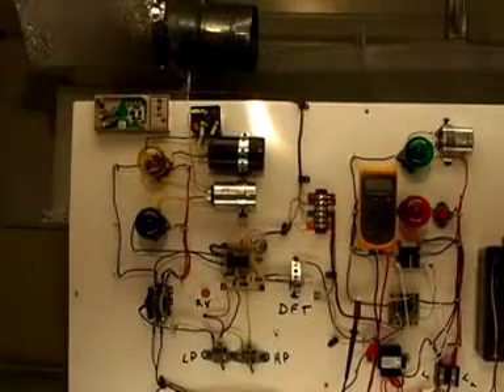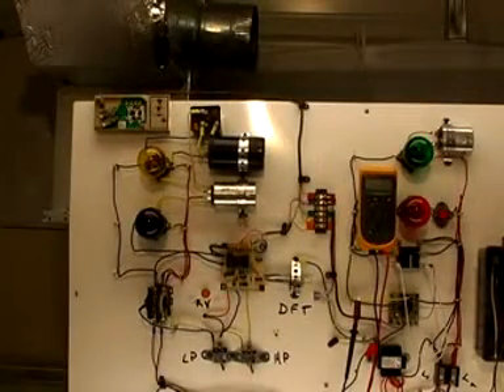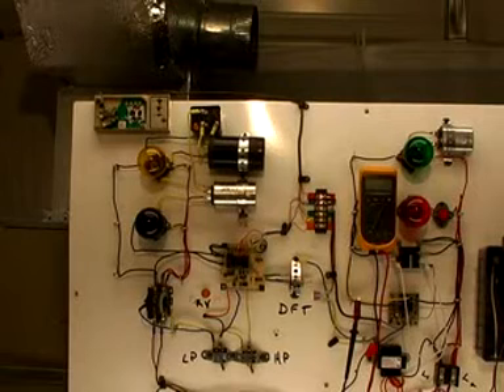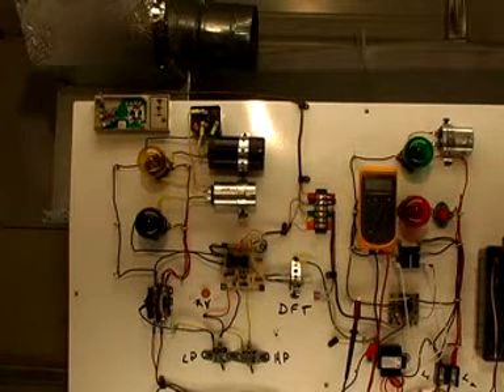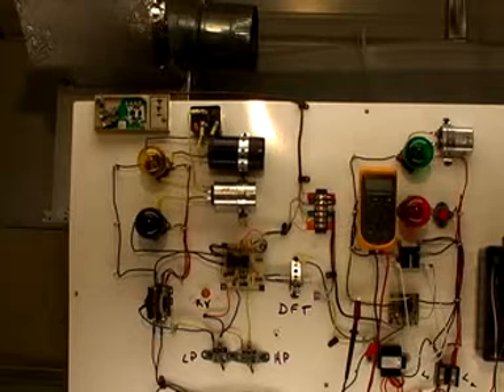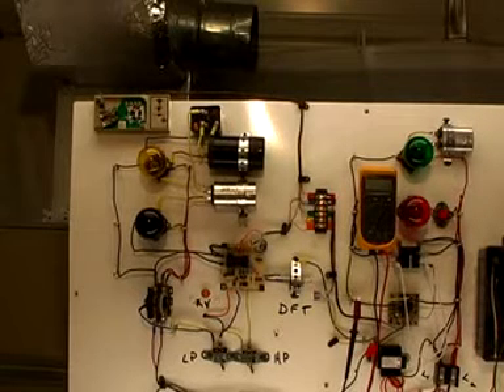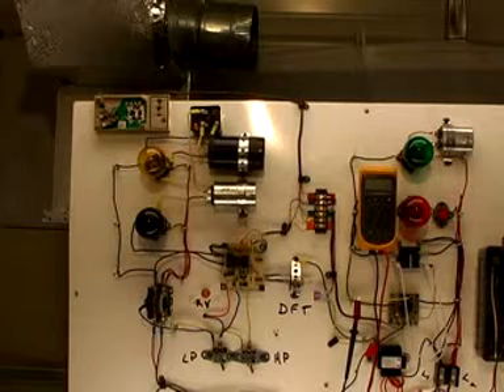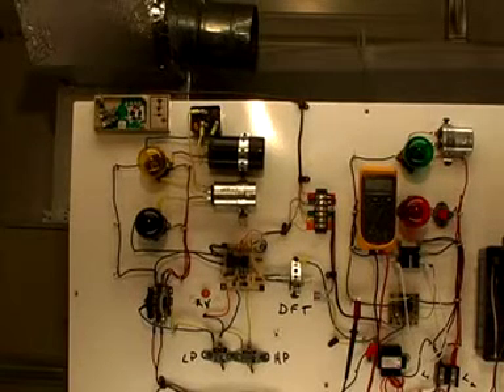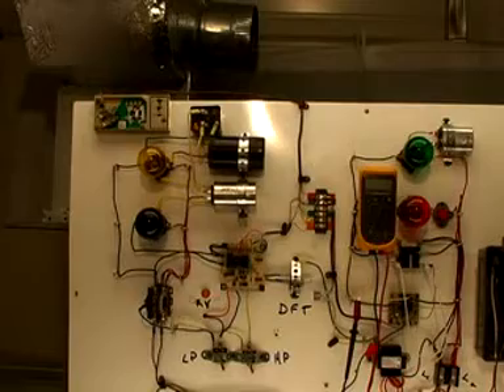So with this crash method, if you're at the air handler, you could just take a jumper and jump from R to the 4 circuits that we use, which is second stage heat, blower, contactor, and reversing valve. Or you can come up to the thermostat and just turn the switches and make set points such that you just get one circuit energized at a time.